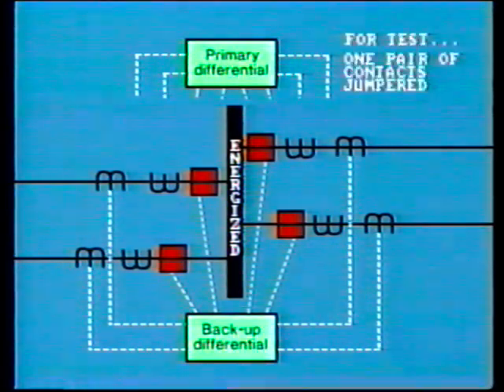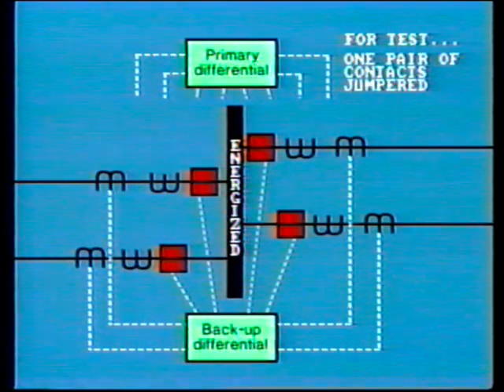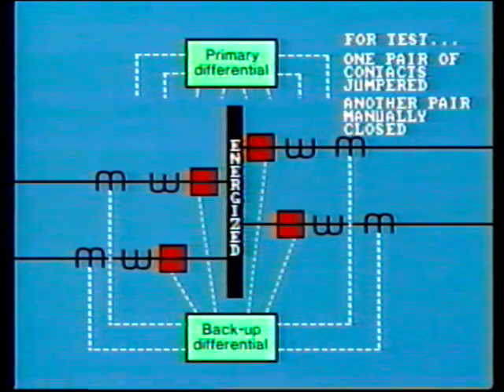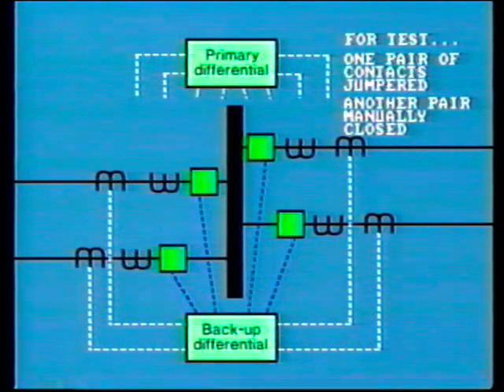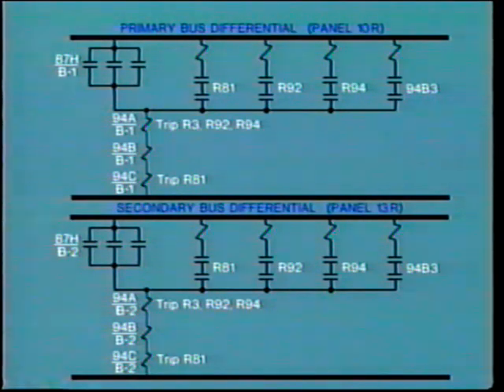As part of the test, one pair of contacts was jumpered and another pair was manually closed. It turned out that these were the wrong contacts, and this led to operation of the redundant differential scheme and so tripped the bus. As in many cases, both of the differential schemes are presented on the same diagram, and it is certainly possible to look at the wrong numbers if great care is not taken.